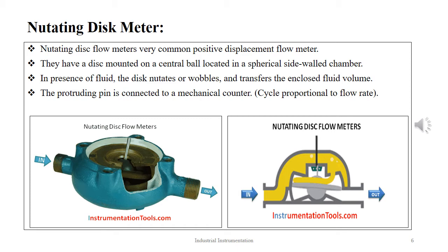The pressure of the liquid passing through the measuring chamber causes the disc to rock in a circulating path without rotating about its own axis. It is the only moving part in the measuring chamber. A pin extended perpendicularly from the disc is connected to a mechanical counter that monitors the disc rocking motion. Each cycle is proportional to a specific quantity of flow.